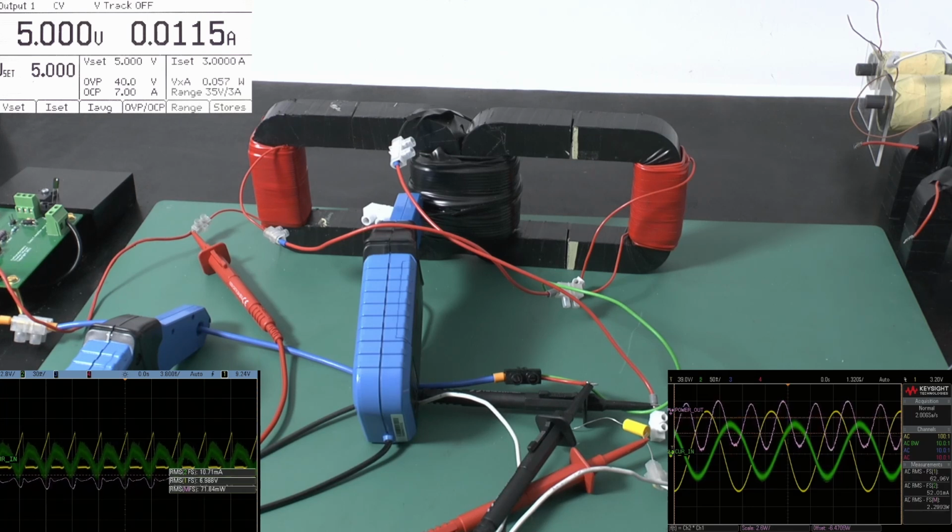That means you consume much more power from your power company, which will fine you for that if you don't take care of your power factor. This can be done by adding a capacitance to the inductor to shift the phase back to the phase of the voltage, so that we are coming back to close to 1. That means our perfect way of transmitting energy to our load or consumer. So we can do that by adding a capacitance.